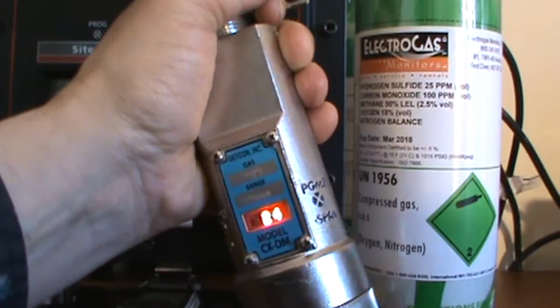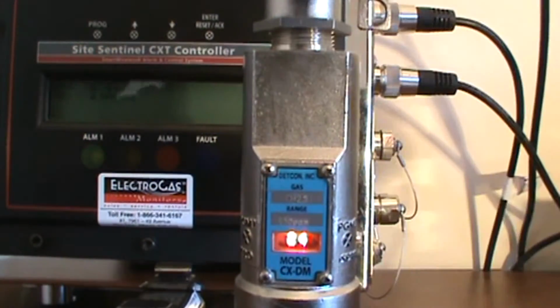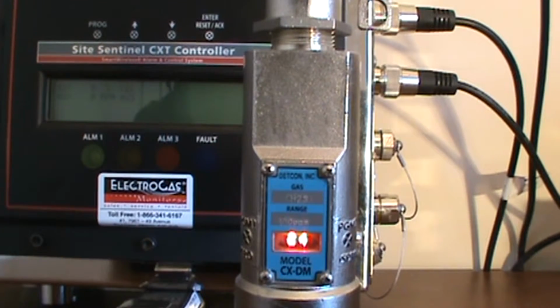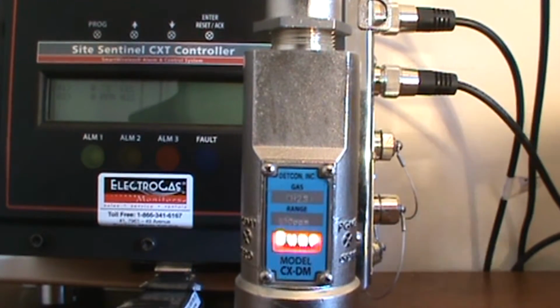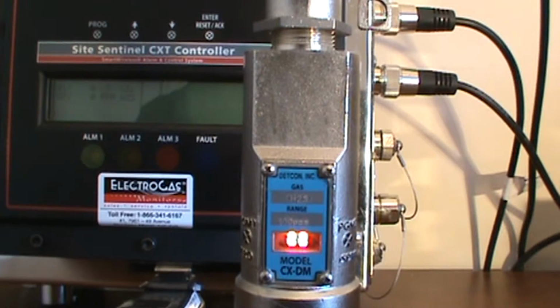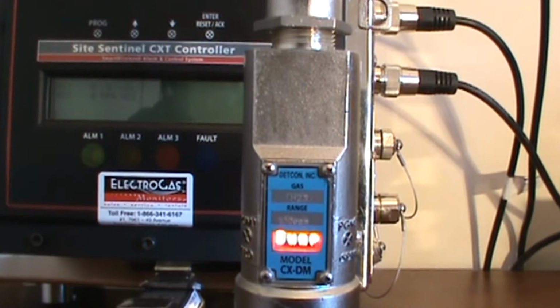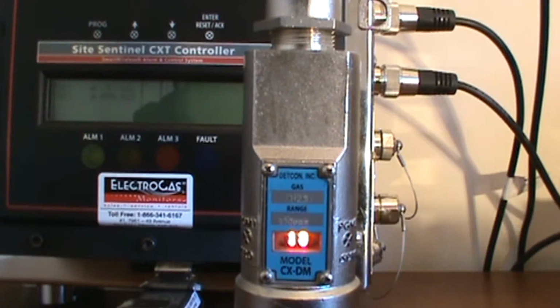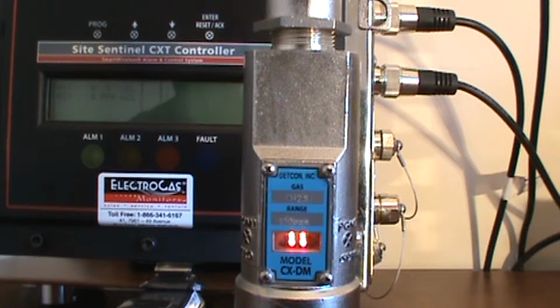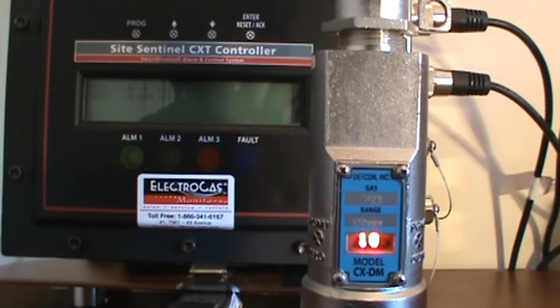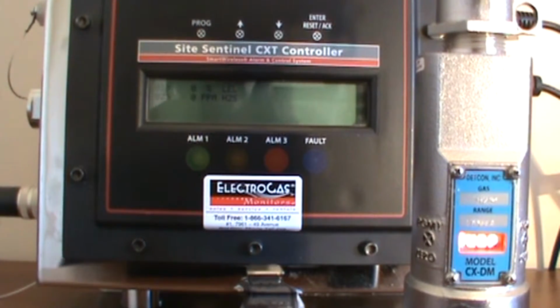So you can simply remove your hose and turn off the gas. And that is a successful bump test using the onboard bump test menu on your sensor. And you must simply now wait for the sensor to fall below an alarm level and your bump test is complete. The third way that you can do a bump test on your sensor is using the inhibit alarm menu on your CXT controller.